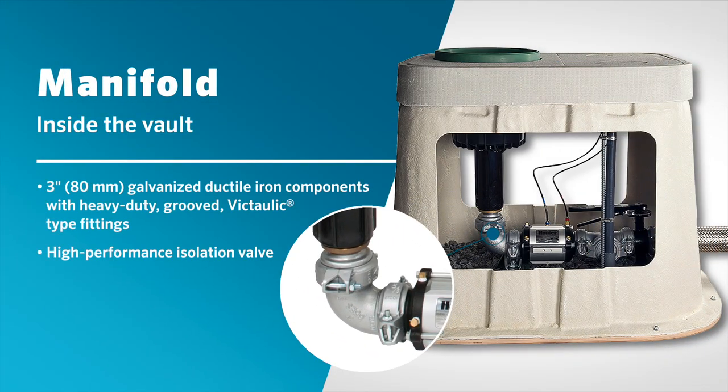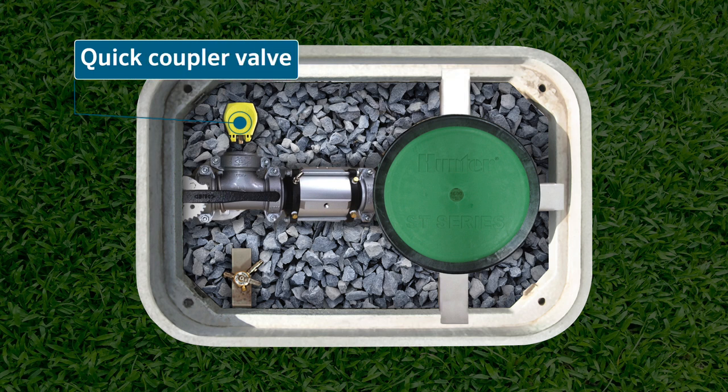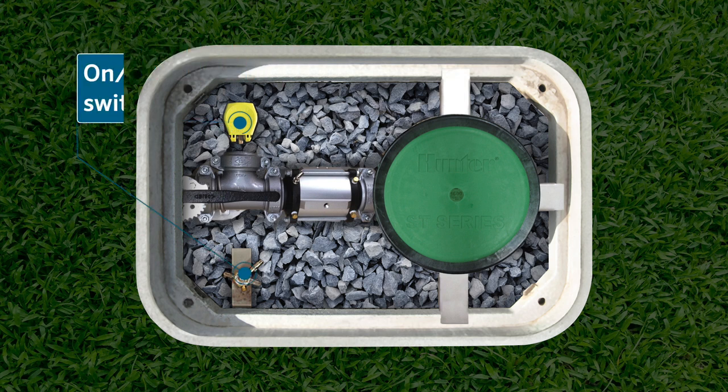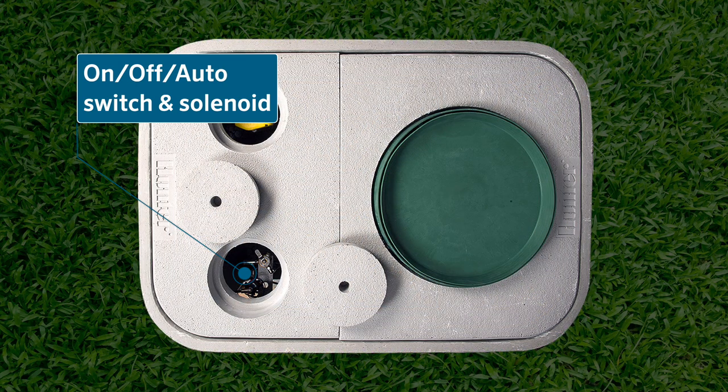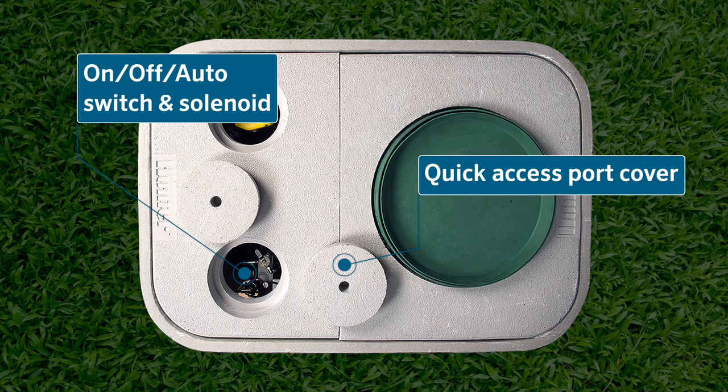Inside the vault, a robust and reliable manifold features three-inch galvanized ductile iron components with heavy-duty grooved Victaulic-type fittings. In addition, the vault comfortably holds a high-performance isolation valve, quick coupler valve, and a slow-opening, low-pressure loss control valve that comes with a remotely located on-off auto selector switch and solenoid. The selector switch and solenoid are located near the top of the vault and are easily accessible by removing the quick-access port cover.